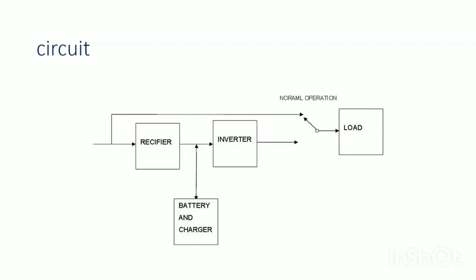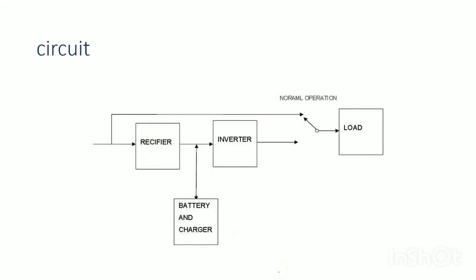In offline UPS, normally the load is directly connected via the main supply path. Only when the main supply fails does the rectifier-inverter path provide power to the load. When the main supply is present, the battery gets charged through the rectifier path, and electric power is provided directly from the main supply to the load.